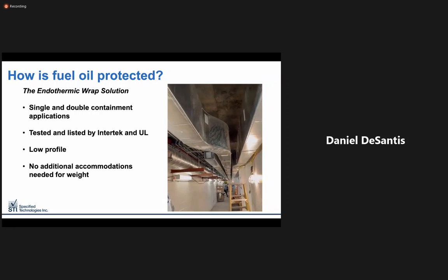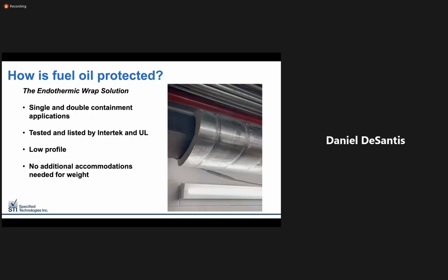As we can see here on a large project completed in New York City, a 16-inch wide spill duct enclosure housing several fuel oil lines was enclosed using endothermic wrap. The application blends seamlessly to the surrounding construction and code requirements for fire resistance are met.